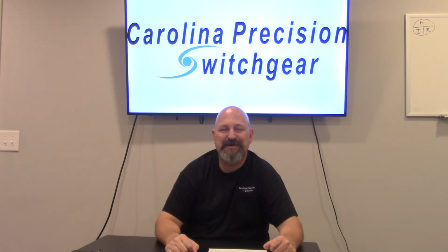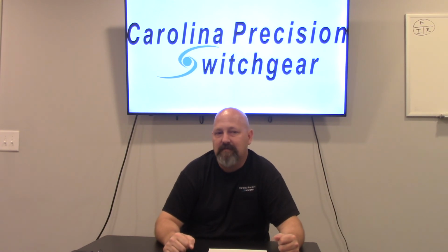So if the cause of the trip of the circuit breaker can't readily be determined, it might be time to get some professional help with it, whether that be your local electrician or a testing company or Carolina Precision Switchgear. Closing into a fault can be extremely dangerous. That is probably the worst time in the life of a circuit breaker. So by all means, if you're unsure, get some help.